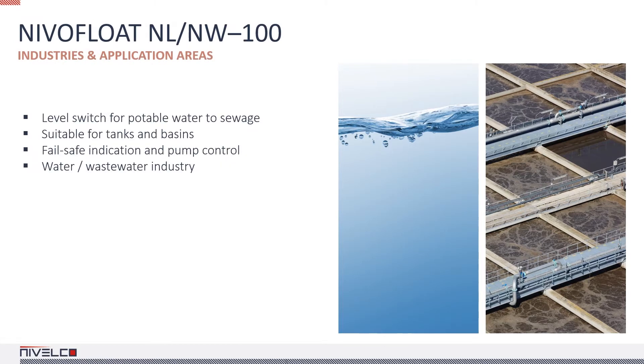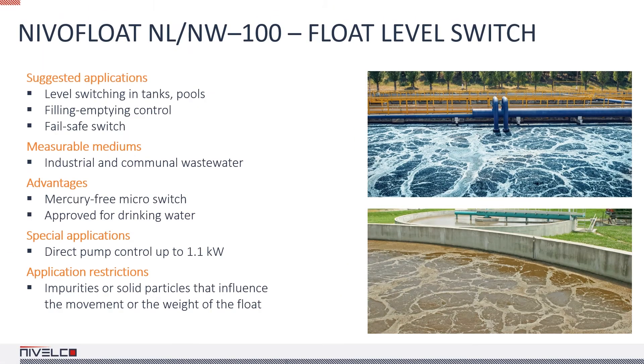NivoFloat level switches are widely used for controlling pumps and failsafe indication in water and sewage processing. In wastewater applications, the float switch must be cleaned regularly, as there may be a large amount of thick slur stuck to it, which can affect its operation. The maximum directly switched power is 1.1 kW. If the switched power exceeds this limit, a relay must be installed for switching.